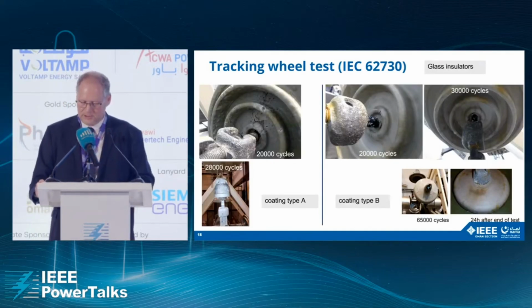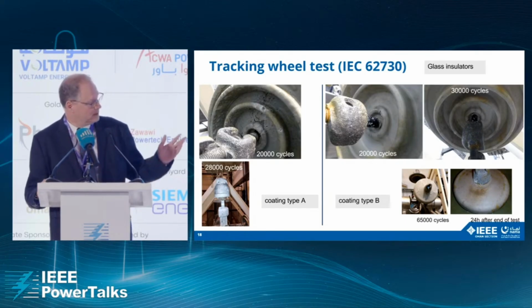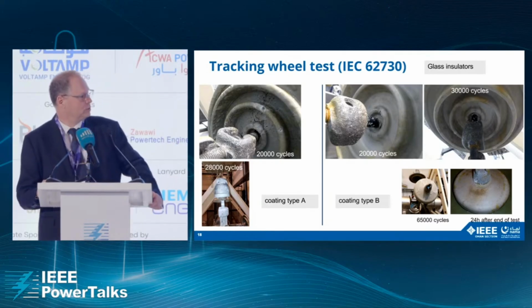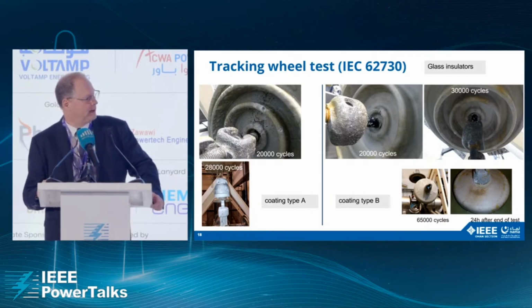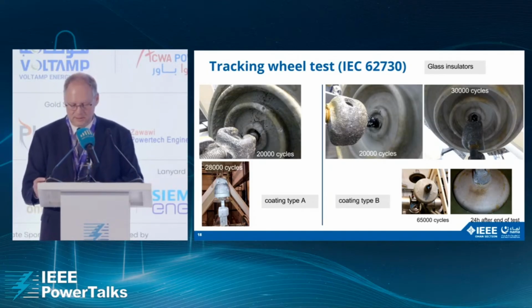The bottom sides of the insulator are typically more impacted given the concentration of electrical activity around the pin. This is where the nature of the silicone itself can make a difference, where you can see here an example of two coatings, A and B, applied on the same insulators. Coating A, after 28,000 cycles, shows complete destruction of the insulator, whereas after 65,000 cycles, when we stopped the test, coating B was still sound and safe.